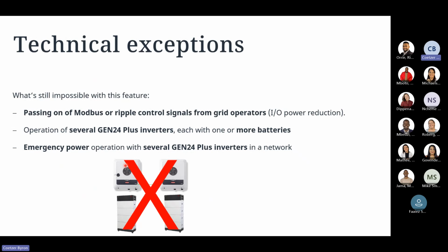So there's a few technical exemptions. What's still impossible with using SBC? The passing on of Modbus or ripple control signals from the grid operators. Making use of IO power reduction is still not possible, as well as the operation of several Gen 24 Plus inverters with each one having one or more batteries.